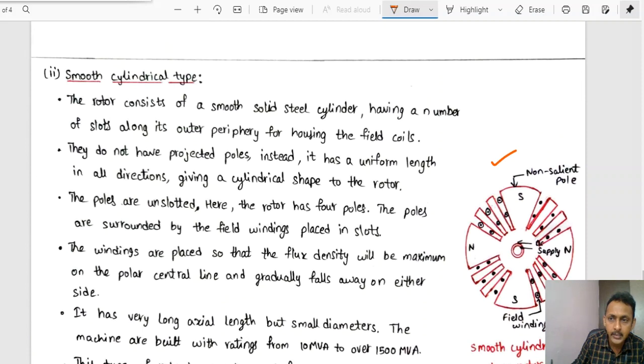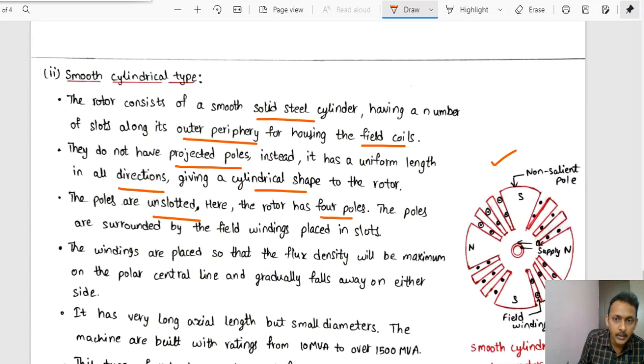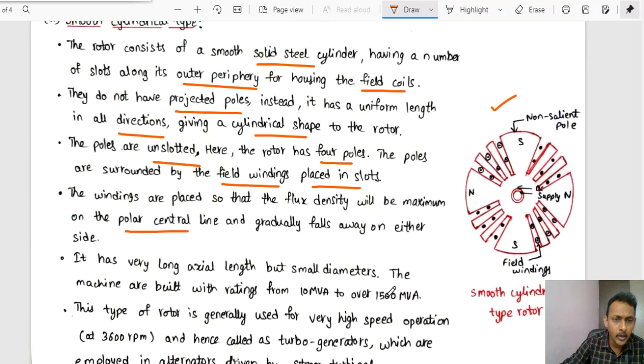With respect to the smooth cylindrical type, this is a non-salient pole type rotor. The field winding is placed in slots along the outer periphery. The rotor consists of a smooth solid steel cylinder with a number of slots to hold the field coils. It has no projecting poles; instead it has uniform length in all directions with a cylindrical shape. The poles are unslotted and surrounded by field windings placed in the slots, so that flux density is maximum on the polar central line and gradually decreases on either side.